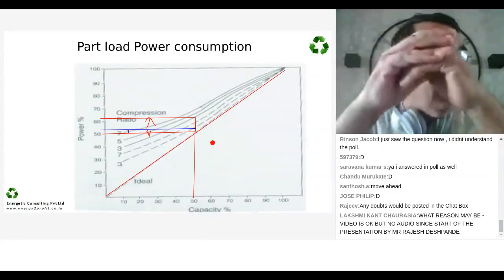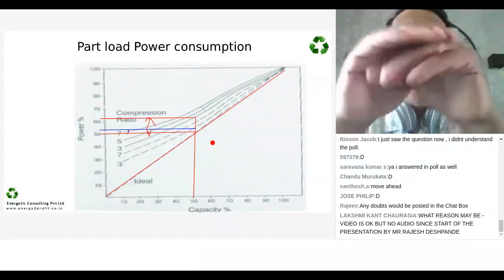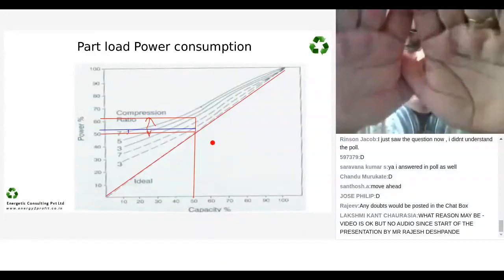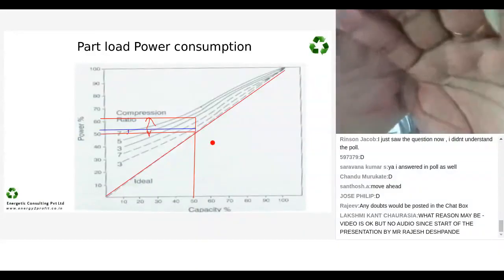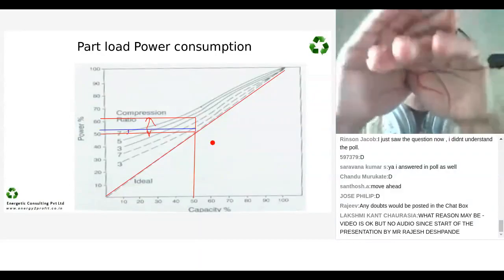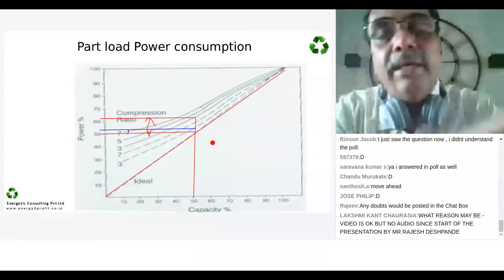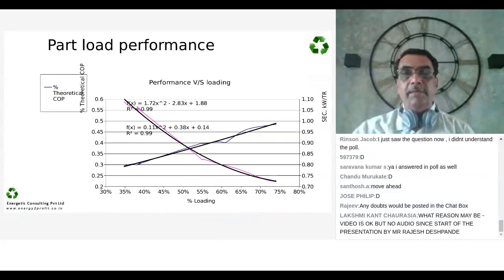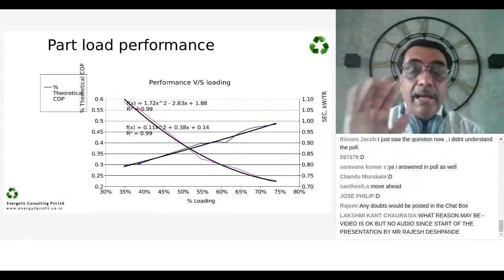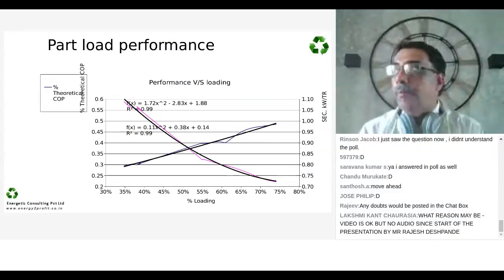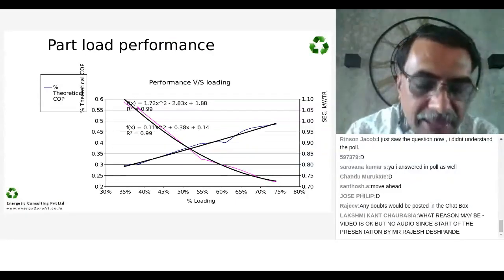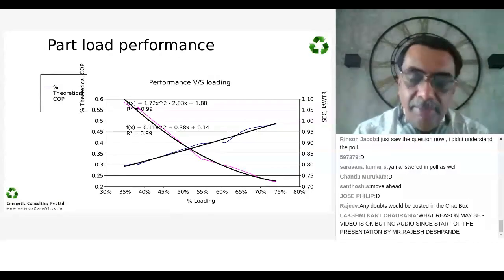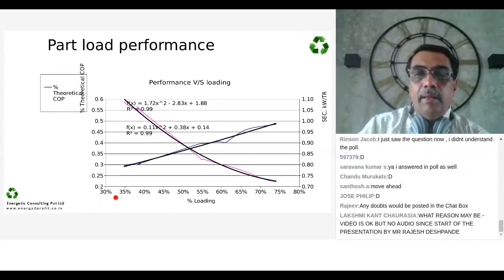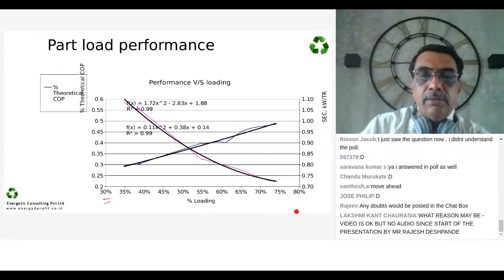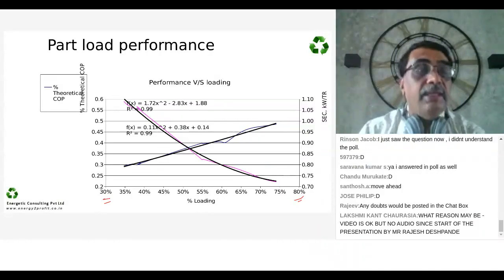Which, in other words, for the same condensing temperature, if you are operating a 7-degree chilled water temperature, your inefficiency at part load is lower. If you are operating at minus 10 degrees centigrade, your inefficiency is higher. That is what it means. This is the actual performance trial which we did on one compressor, screw compressor, HVAC system, chilled water at 7 degrees centigrade. We did trials on the 300 TR machine.